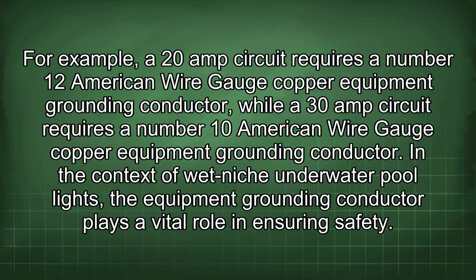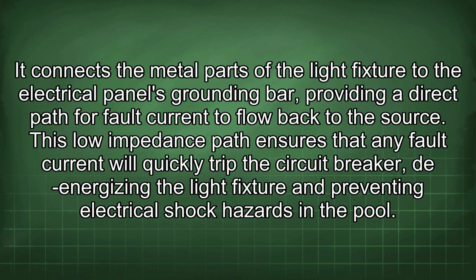In the context of wet niche underwater pool lights, the equipment grounding conductor plays a vital role in ensuring safety. It connects the metal parts of the light fixture to the electrical panel's grounding bar, providing a direct path for fault current to flow back to the source. This low impedance path ensures that any fault current will quickly trip the circuit breaker, de-energizing the light fixture and preventing electrical shock hazards in the pool.